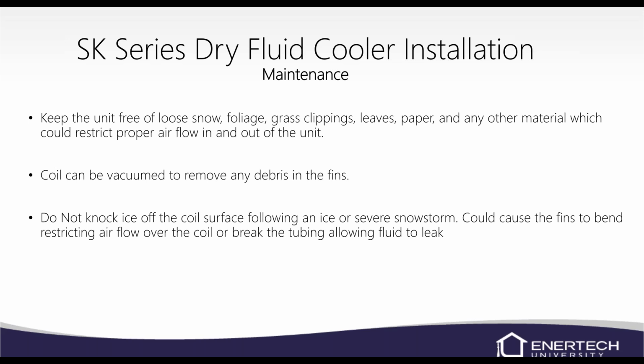Maintenance, there's not a ton to do on here. It does have an air coil, so you'll have to clean it. But make sure that the unit doesn't have any snow buildup. There's no bushes covering it up. Keep the grass away from it. Any leaves or paper, just like a standard condenser air source heat pump sits outside. And make sure there's no cottonwood or anything like that plugging it up and restricting the airflow.